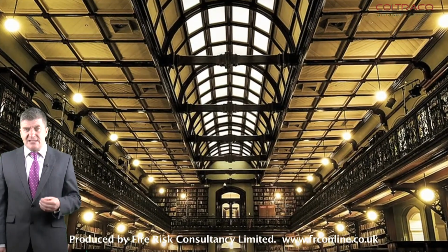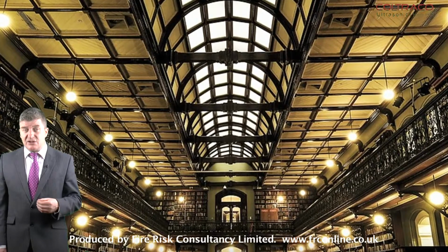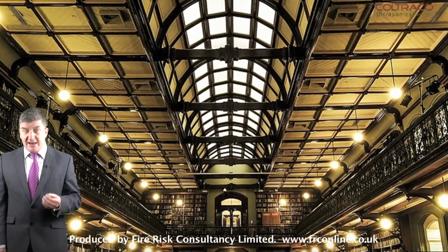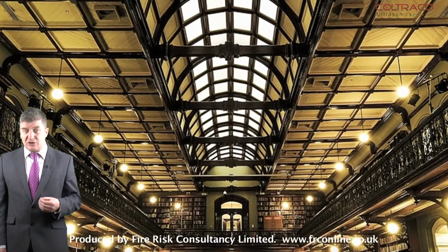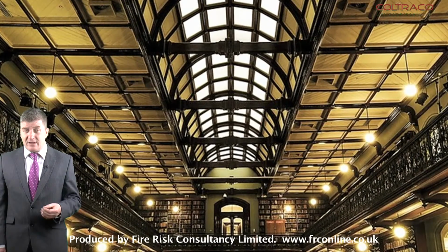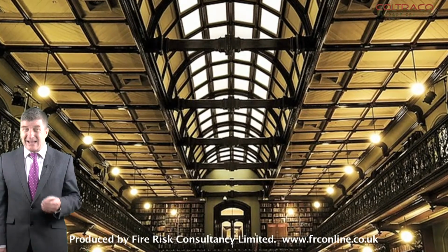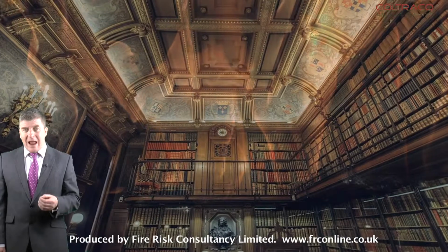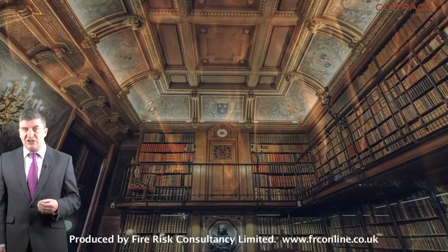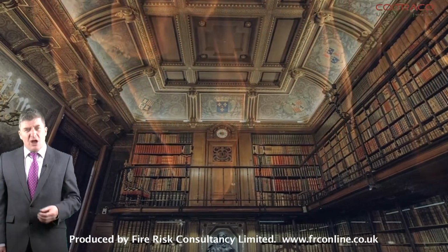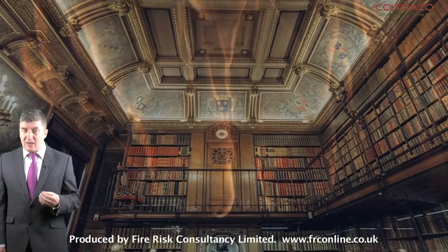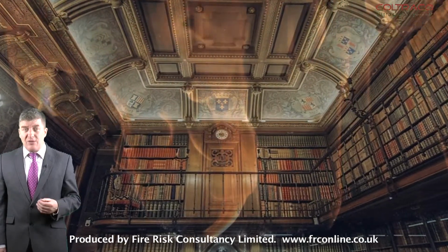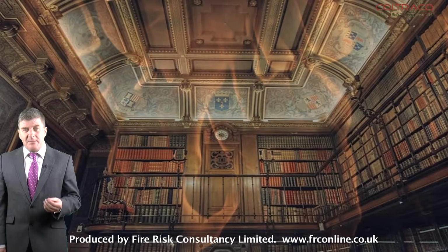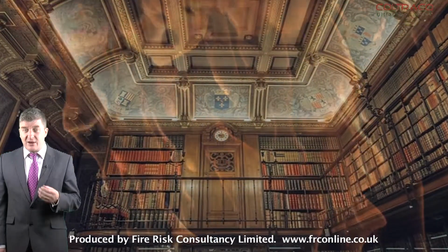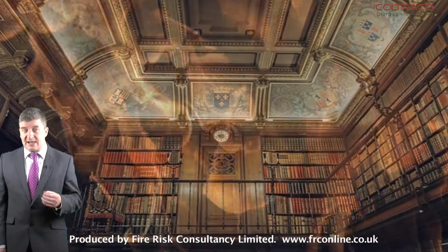Where the integrity test reveals increased leakage that would result in an inability to retain the extinguishant for the required period, remedial action has to be carried out. Where it is established that changes to the volume of the enclosure or to the type of hazard within the enclosure or both have occurred, the system shall be redesigned to provide the original degree of protection.